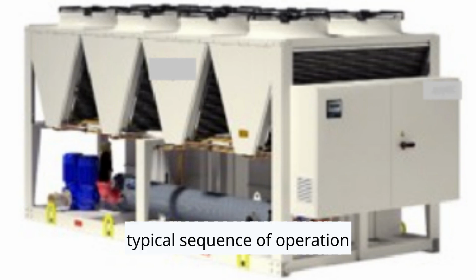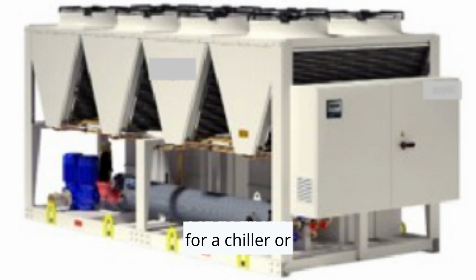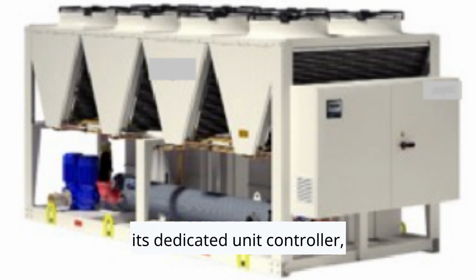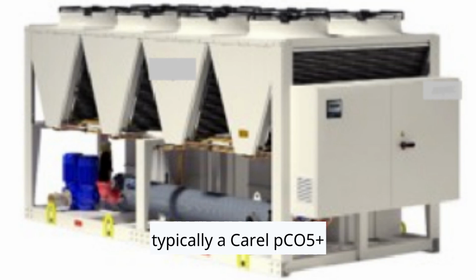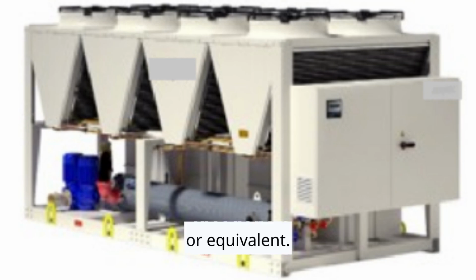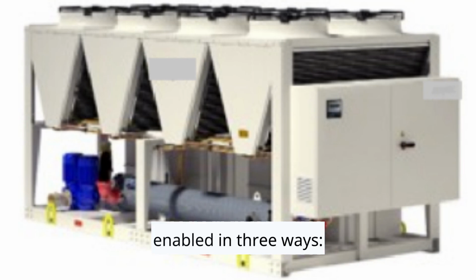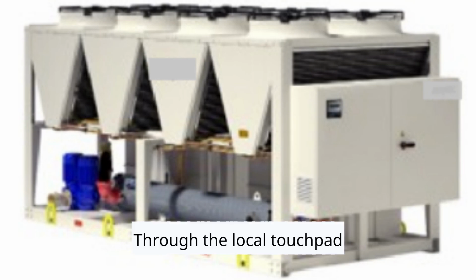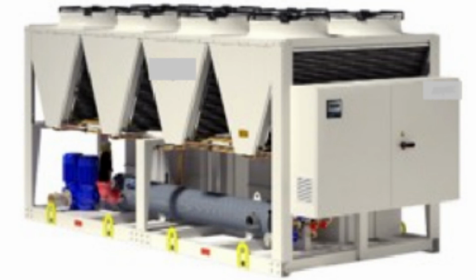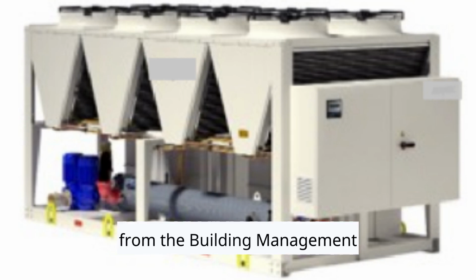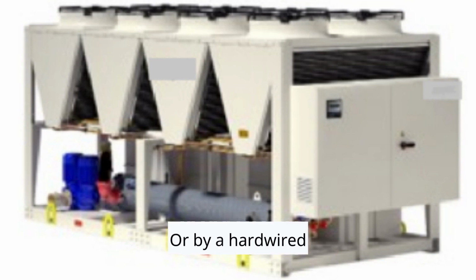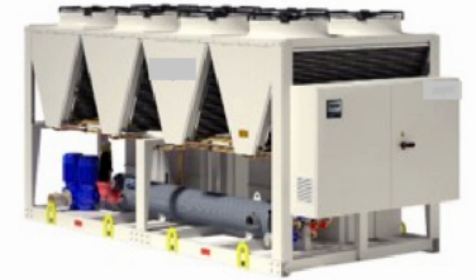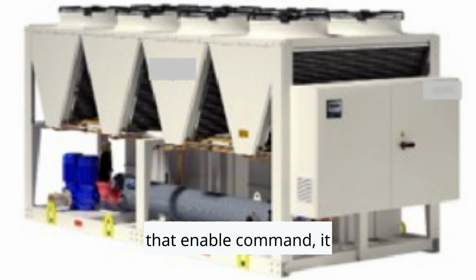Let's walk through the typical sequence of operation for a chiller or heat pump. The chiller or heat pump is managed by its dedicated unit controller, typically a Carel pCO5 Plus or equivalent. The system can be enabled in 3 ways: through the local touchpad interface, via a BACnet command from the building management system, or by a hardwired enable signal.